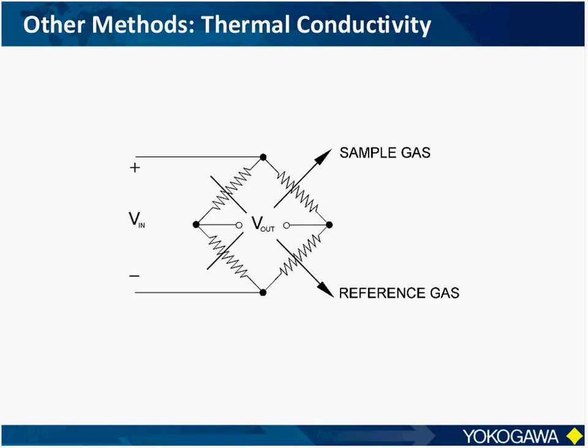Some things to consider about this method. One is that a reference gas is required. Also, the detector must be kept at a stable temperature through the use of heaters or ovens. These ovens also require warm-up time to reach these target temperatures. Now, it's also recommended that the flow rate of the sample gas be held constant to prevent cooling of the filaments due to increased flow rate versus actual changes in thermal conductivity. And also, since thermal conductivity versus the concentration of increasingly heavier hydrocarbons is not a linear relationship, multi-point calibrations with blended gases may be necessary in certain applications. And lastly, it would be fairly difficult and rather expensive to restore this type of analyzer to working order in the field if it is significantly contaminated with oil.